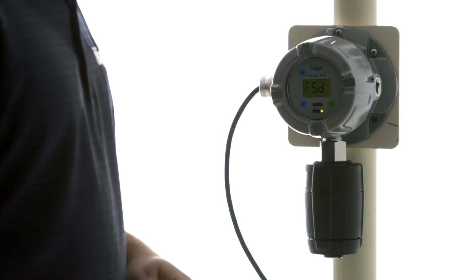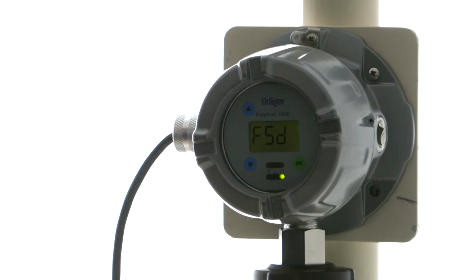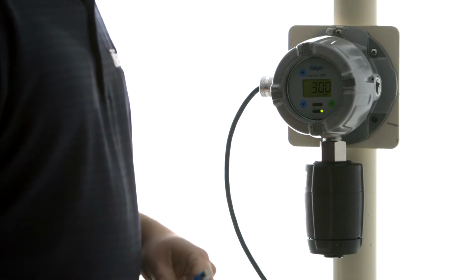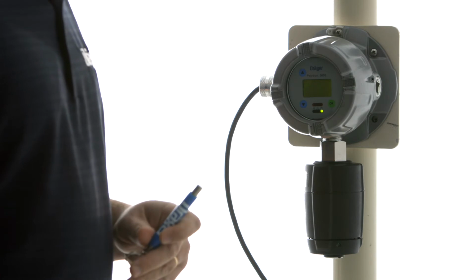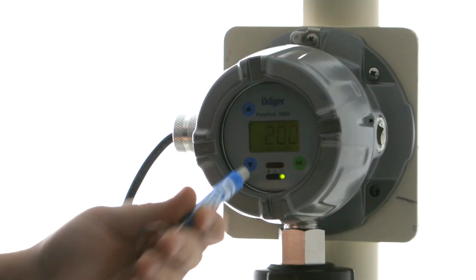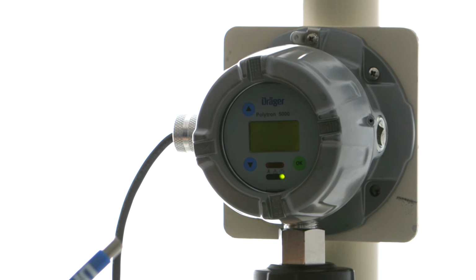As we move along, we now have a full-scale deflection. That is selecting the value of your 20 milliamp signal. The sensor can have a range of 0 to 300 ppm, but the 4 to 20 milliamp can be adjusted below 300 ppm. And the full-scale deflection is what's used to do that. And if we hit OK, we can see that 300 ppm is currently selected. We can tap the down arrow and select from predetermined full-scale deflections down to 50 ppm.